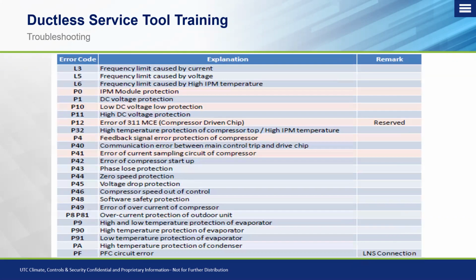Okay, and you can see on here, there's a bunch of different codes that will come up depending on various situations. The code will actually appear on the tool, followed by a brief explanation, which they have listed here, of what's going on. So chances are you're probably not going to have to use this menu, but it's definitely something that I wanted to encourage you guys to become familiarized with, because each different device comes with its own check codes that we need to confirm we're reading correctly.